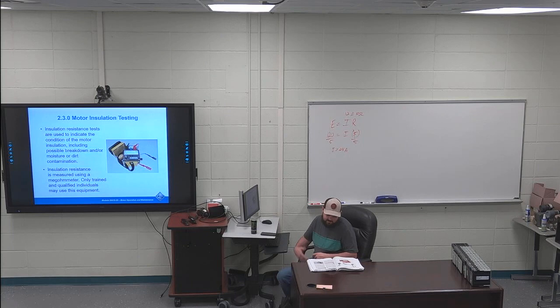Insulation resistance test. Like you should have known already, insulation resistance tests are done with megohmmeters, or meggers. But I've got the second warning on page 17 highlighted: when using an insulation tester, the motor frame must be directly connected to the building or earth ground.